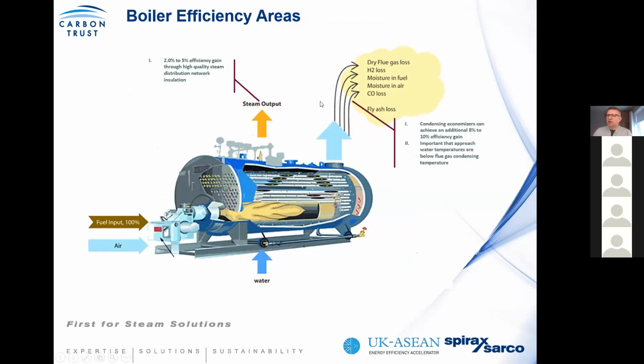You can have what's called a standard economizer, which basically only cools the flue gas temperatures, or you can have a condensing economizer. The condensing economizer uses the latent heat entrained within the flue gases, because in general, your boiler could be about 90% efficient, due to the latent energy contained in the flue gases which is not used in the standard boiler. Your standard economizer will not recover this energy; it will recover the sensible heat from the flue gases. However, a condensing economizer can give you about an 8 to 10% efficiency gain. It's important that you have a cooling medium at a temperature lower than the flue gas condensing temperature. So it's ideal, for example, where you have high makeup water demands in your boiler, that you'd use a condensing economizer, because you'll get that high energy input to preheat boiler makeup water.